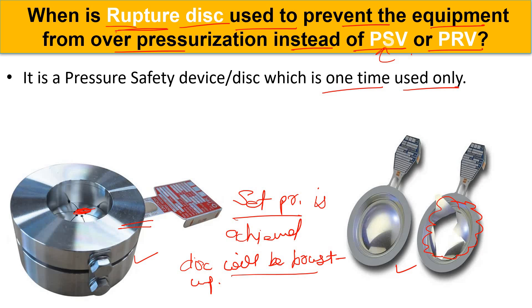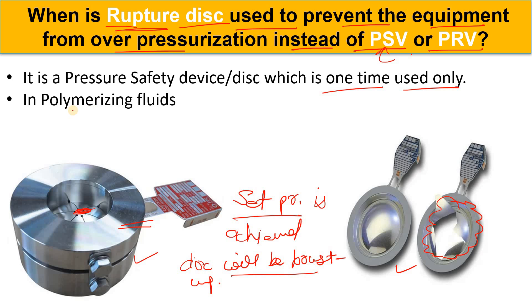The question is: when is the rupture disk used instead of PSV or PRV? One application is in polymerization fluid — whenever we handle polymerization fluid, we use the rupture disk instead of PSV or PRV. The viscosity of this fluid is very, very high, which could cause blockage if we are using a PSV or PRV.